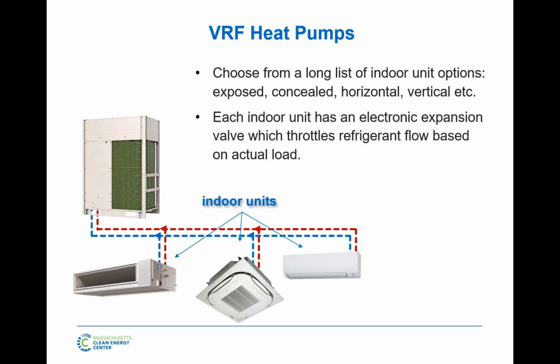And in here, you'll find that expansion device, that thermal expansion device, one of the 4 components of the refrigeration cycle. In VRF, we call them electronic expansion valves, and they're not mechanical. Thermal expansion valves, we call them. Basically what that means is they're controlled by a controller. So this controller looks at the refrigerant temperatures in and out of the coil, and it decides what it wants the valve to do. So what I mean by that is each of these valves is about a 1/4 inch thick and opening, circular, and has about 2,000 positions.